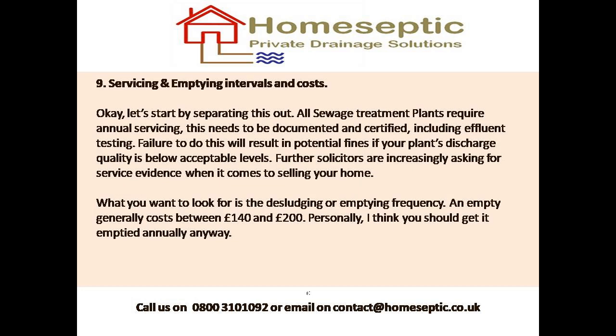Okay, servicing and emptying intervals and costs. Generally a de-sludge should cost you about 140 to 200 quid. You should really get it emptied annually anyway. I think that if you have a sewage treatment plant, you should get it emptied annually at the service. You need to get it serviced these days. So if you have a sewage treatment plant, you need to make sure that it gets serviced annually, and that within that service you get an effluent test or some form of assurance around the effluent quality.